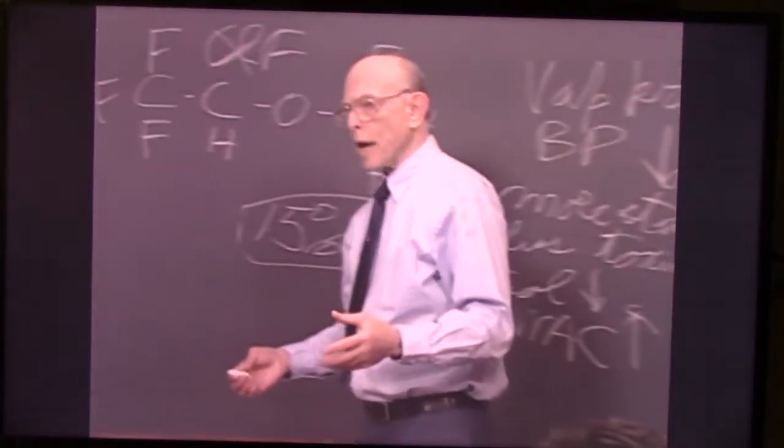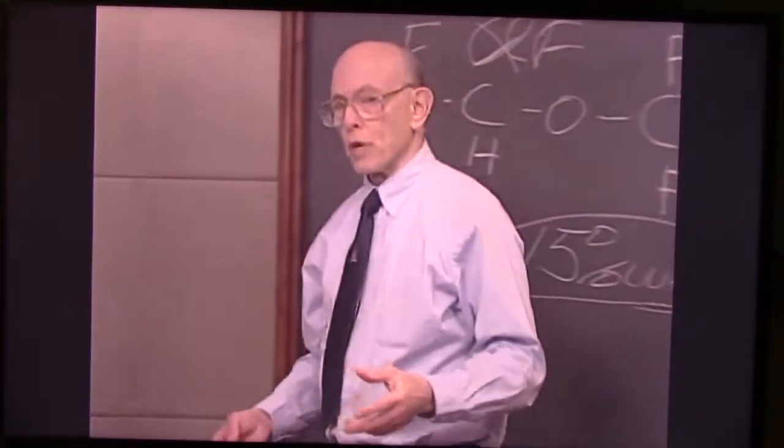How can we get drying of the absorbent? How can that be? It's sitting in that closed container. Well, you get drying of the absorbent if you have high gas flow rates through the absorbent for an extended period of time. Right. So if you give an anesthetic, and at the end you turn off the oxygen, there's no problem.